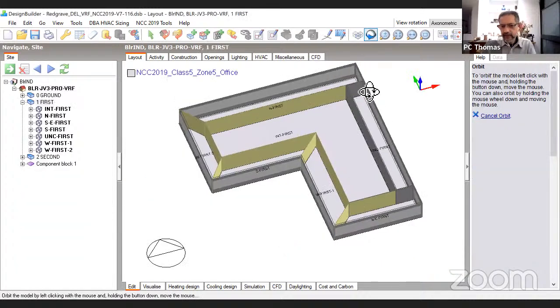This is a real physical partition, so it is made out of some opaque material. These partitions are actually non-existent. They are virtual or imaginary partitions, but they are used to do sizing of air conditioning systems, working out what the temperatures and comfort, etc., are in each of these areas close to the perimeter.